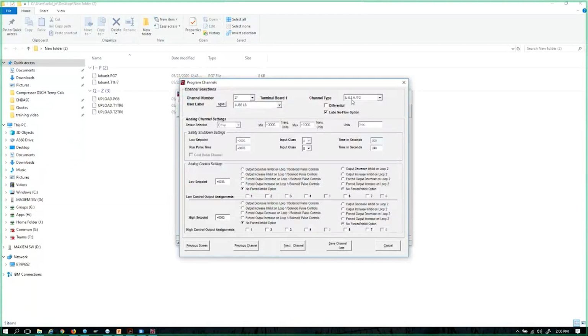We configure the software as an analog channel, 0 to 5 volts, and we simply do one thing. We come down, once we've selected 0 to 5 volts, this lube no flow option goes from a gray out, where we can't access it, to a dark color, and we can check this box. And as soon as we check this box, all of this populates for us. It selects it as other. It scales it from 0 to 1,000 seconds. It grays out the low set point to where we cannot edit it because it's irrelevant, and it only looks at what we call the high or the run pulse time. And we can see here the kill is set to 70 seconds. We also have a Class B timer for startup purposes, and we have it set to 240 seconds.